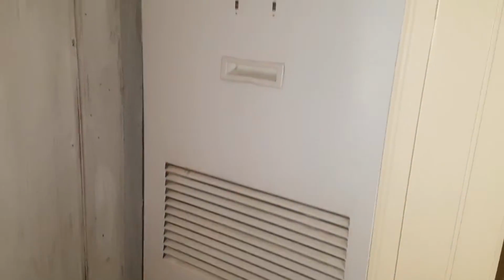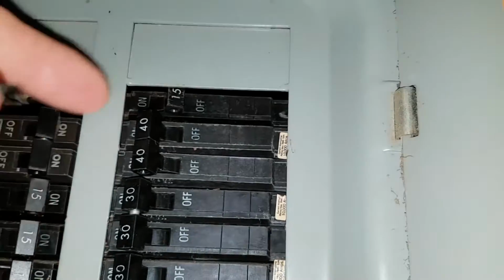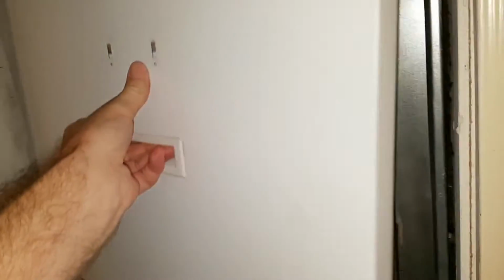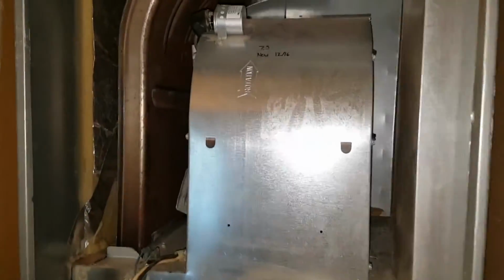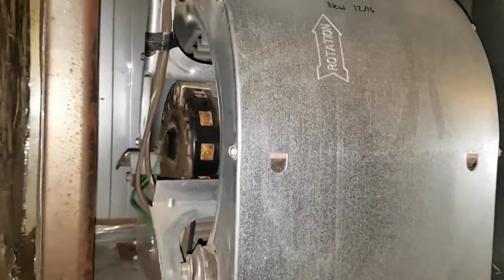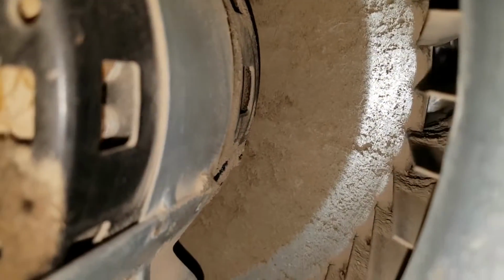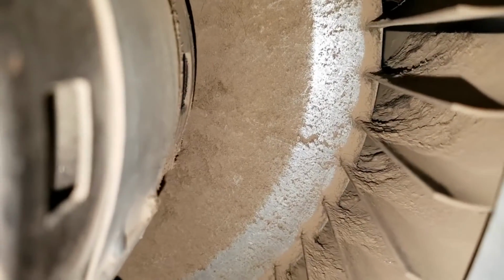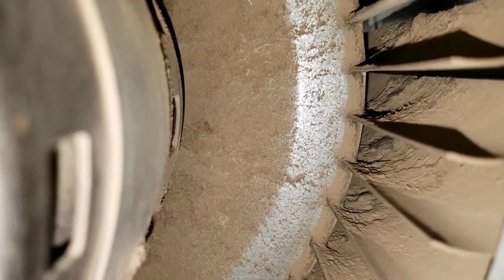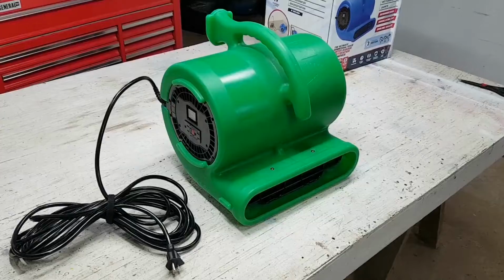Wherever the duct vac hose is installed, I need to make sure that I don't suck any debris or dust into the HVAC unit or any other heat exchangers in the system. Maybe I should have cleaned the furnace fan before attaching the duct vac to the supply side and cleaning it. Some of this dust from the furnace fan may have been drawn further into the HVAC unit of this mobile home. Not much of a return here to clean behind the filter, but you see how dirty the fan is.